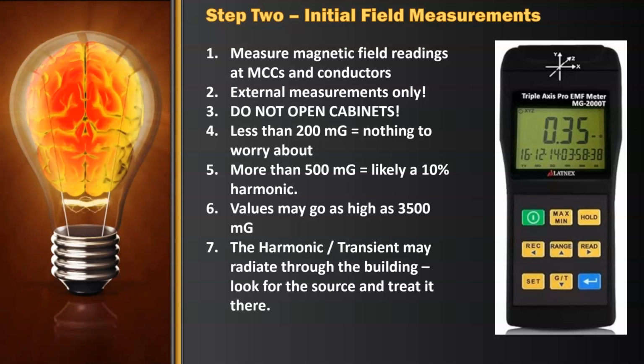This is a triple axis meter, so it allows us to measure in any direction and to measure magnetic field readings at different parts of the system. I don't open up the MCC, I don't take covers off equipment. I just use this to measure the magnetic field, the milligauss readings. Don't open the cabinets up. Might need to do it later. If you want to confirm something, you might need to put in a power quality analyzer, but this is a good way to just measure that.